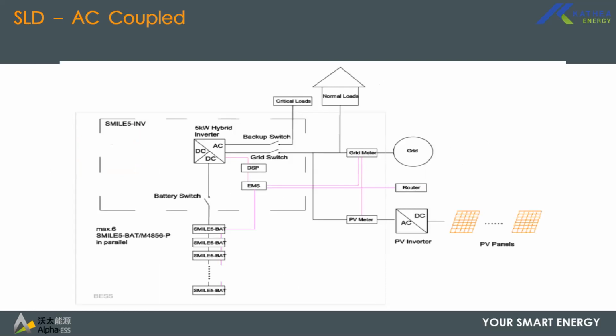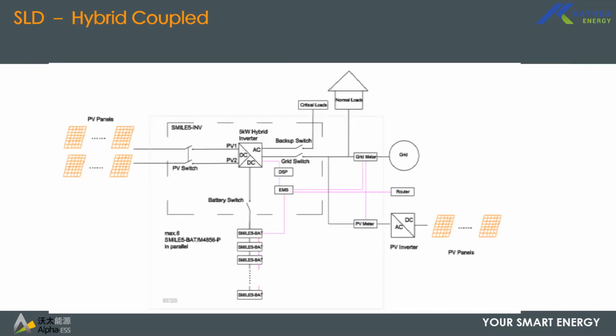So this is basically an AC coupled setup where you have a PV inverter. So basically you would have your PV inverter and then your PV meter daisy chained with the grid meter to the management system, and then all the other setup will be the same as that of DC, except that for AC coupling, the Alpha will not have PV installed to it. And then for the hybrid system, this is the SLD. You have your PV inverter, PV meter, daisy chained with grid meter, and then you have PV to the PV inverter, and then you have another PV array direct to the Alpha system. So this is basically the SLD for it.